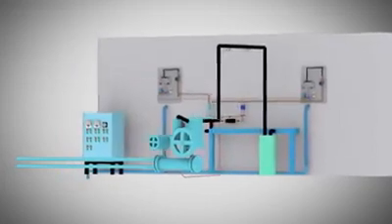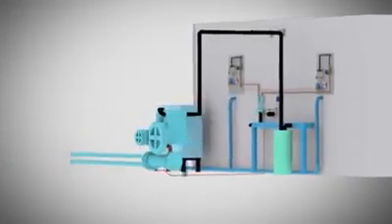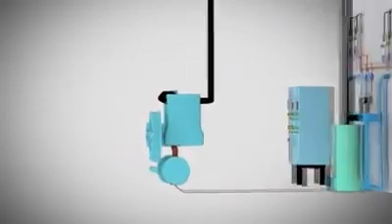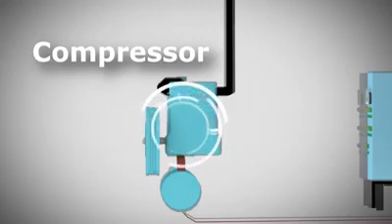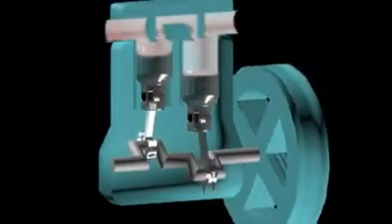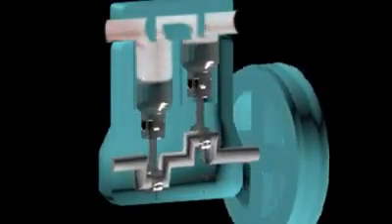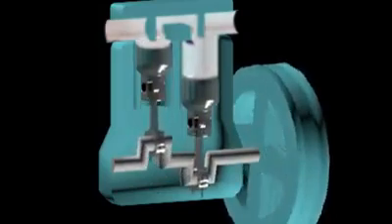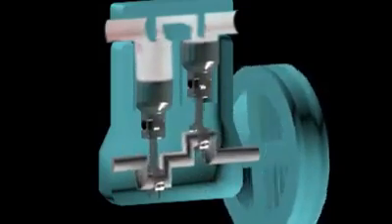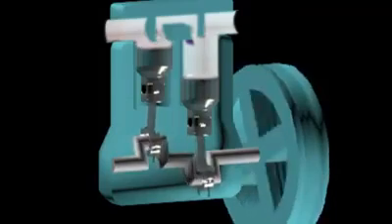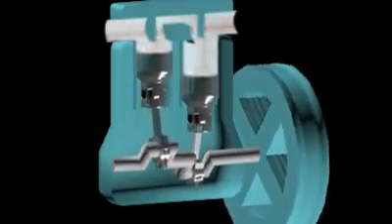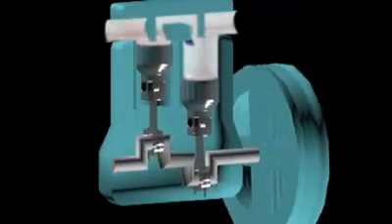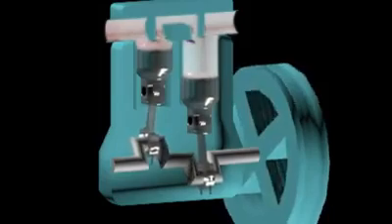The basic components of any refrigeration system working on a vapor compression cycle are the compressor, condenser, thermostatic expansion valve, and evaporator. The compressor is used to compress the refrigerant, producing vaporized refrigerant high in temperature and pressure. The raising of the refrigerant pressure will cause its saturation temperature to rise so that it is higher than that of the cooling substance in the condenser. The compressor also promotes circulation of the refrigerant by pumping it around the system.